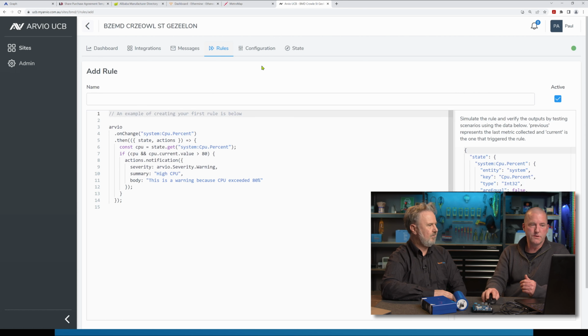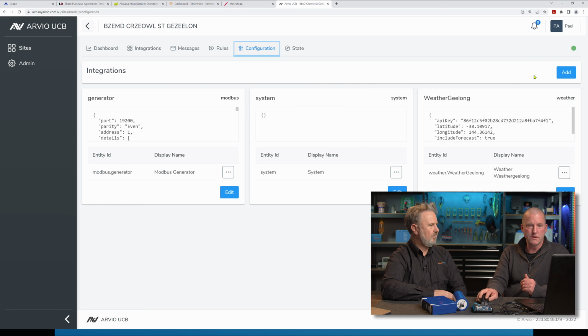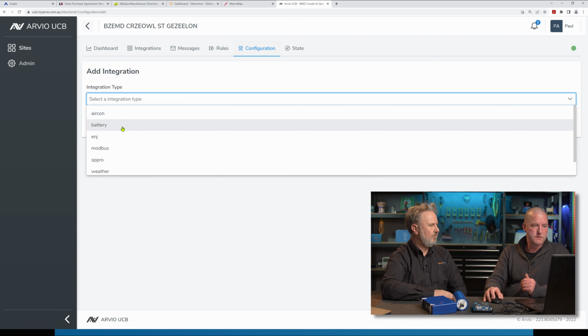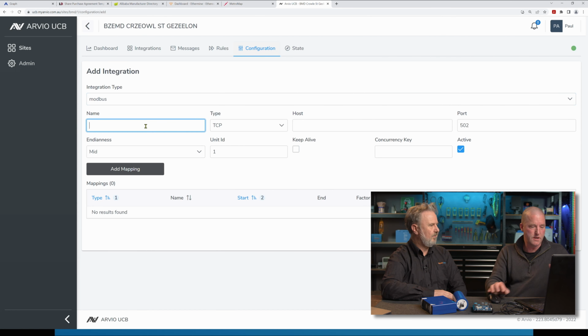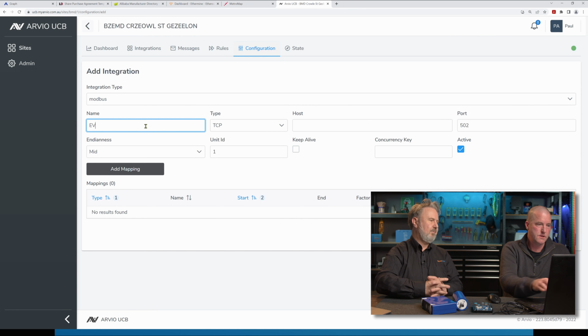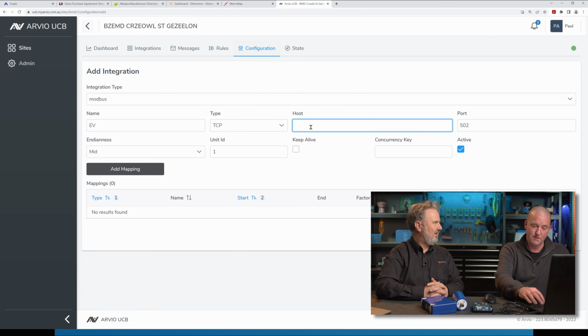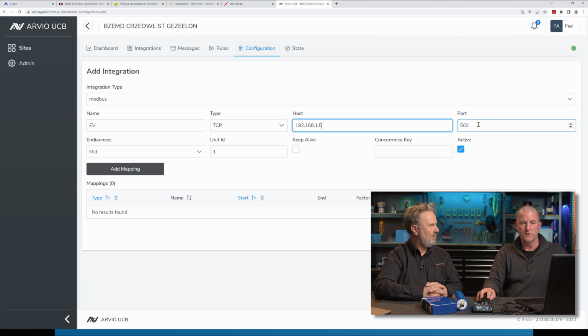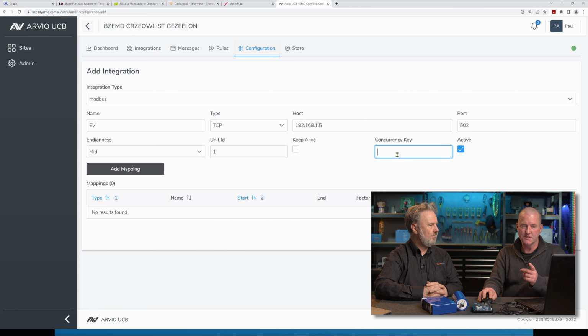Then you go into your configuration here and add the device - a Modbus device - give it a name like EV charger. You could even scan for the TCP address, or just enter it, like 192.168.1.5, whatever it's going to be. The port number is normally 502 for Modbus. Then you set the endianness, this is - this is a funky name for how it talks on the data, which is on the Modbus map information you get from the manufacturer.